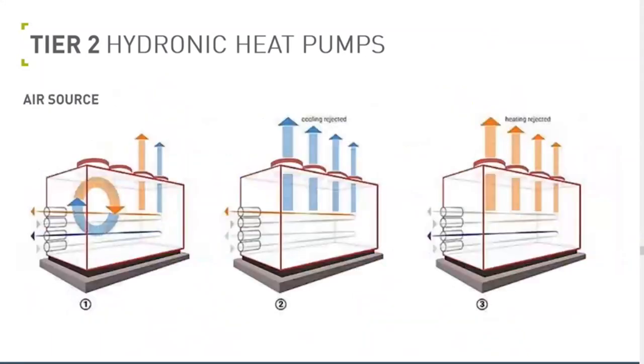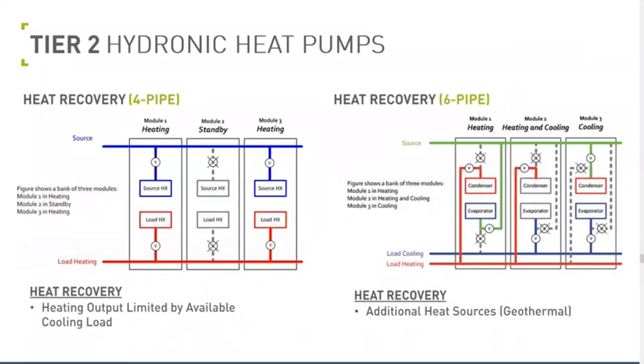Tier 2 continues on that. I see I only have 10 minutes left, so I'm going to brush through some of this, talking a little bit more about hydronic heat pumps and what types of options there are. There are heat recovery options, which generate simultaneous heating and cooling. They have increased efficiency when you're generating both. They do not have increased efficiency when you're generating only heating and no cooling. It really needs to be simultaneous.